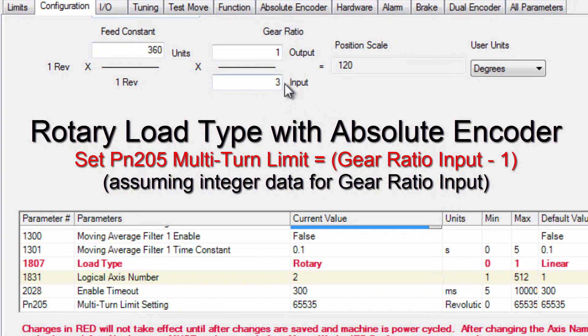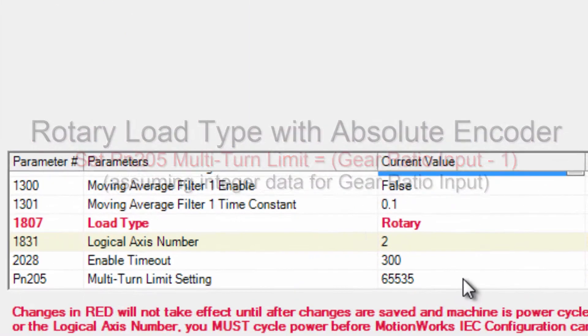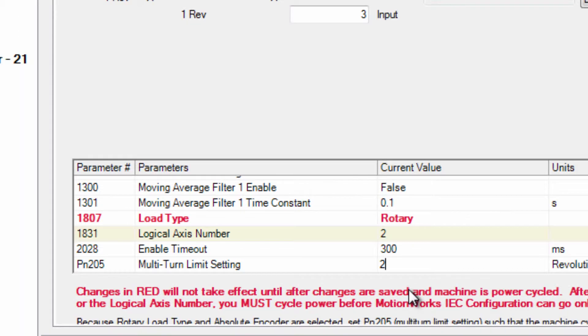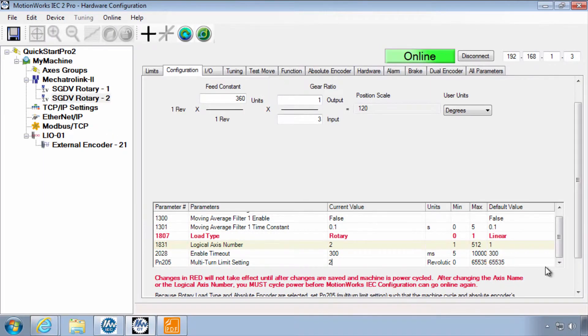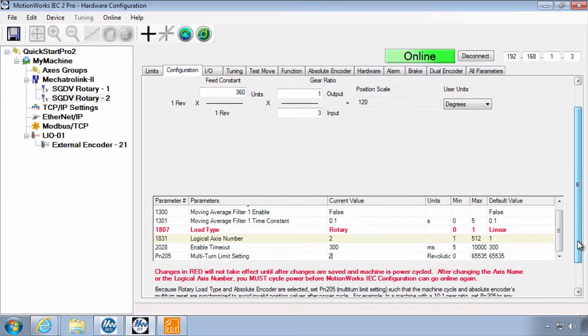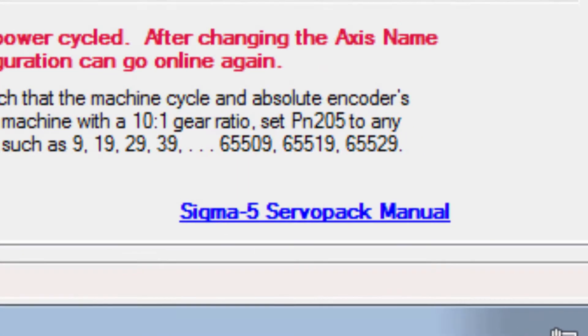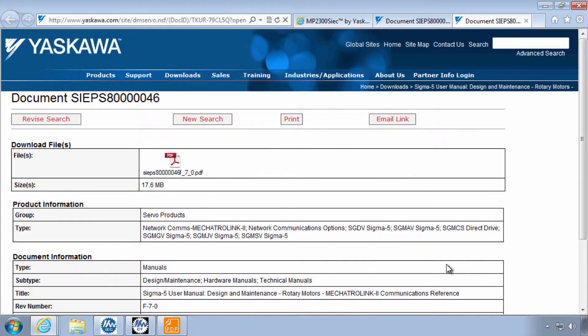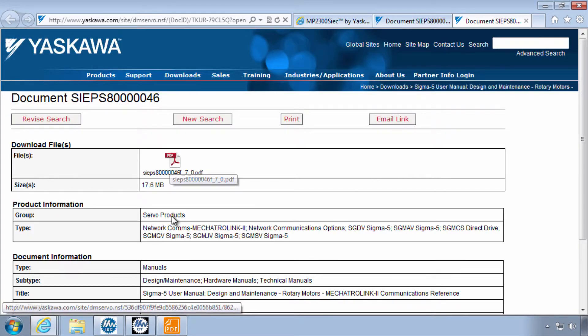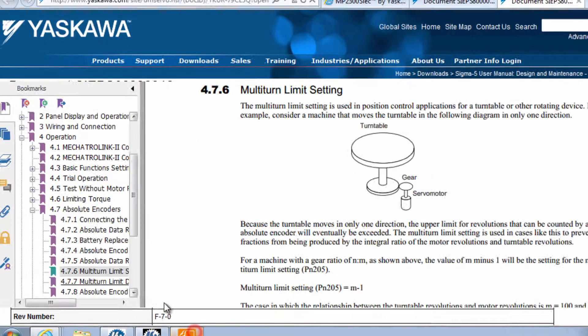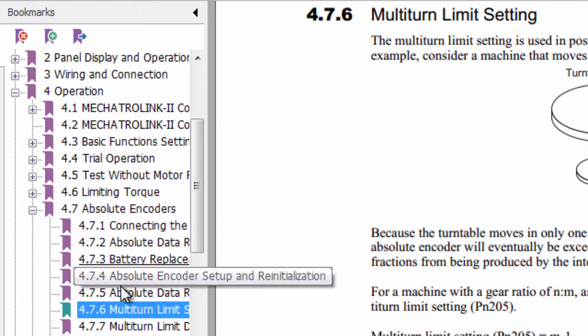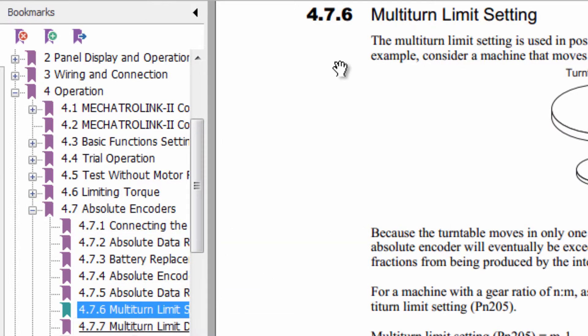We should set that to the gear ratio input which we have set as 3 minus 1. So whatever we have in this area minus 1. We'll put in 3 minus 1 is 2. For more details on the absolute encoder and the multi-turn limit you can look at the Sigma 5 servo pack manual and refer to chapter 4.7.6 multi-turn limit setting.